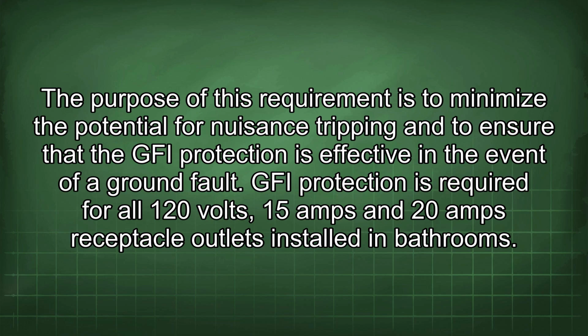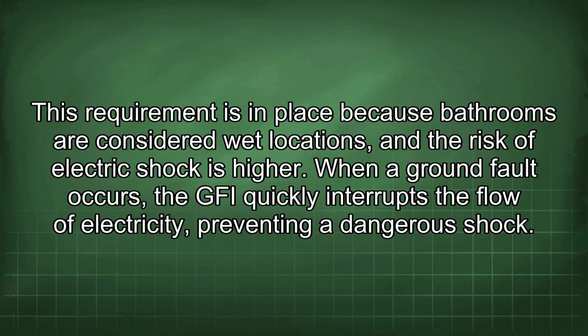GFI protection is required for all 120 volt, 15 amp and 20 amp receptacle outlets installed in bathrooms. This requirement is in place because bathrooms are considered wet locations and the risk of electric shock is higher. When a ground fault occurs, the GFI quickly interrupts the flow of electricity, preventing a dangerous shock.